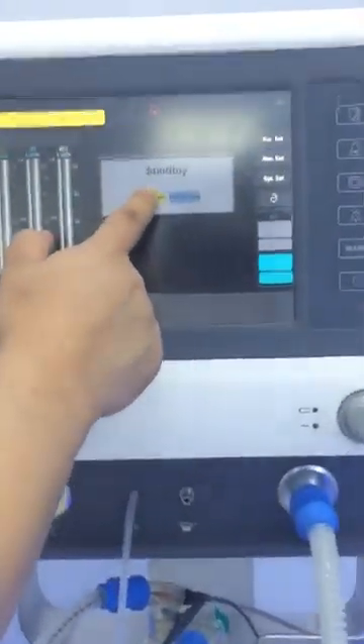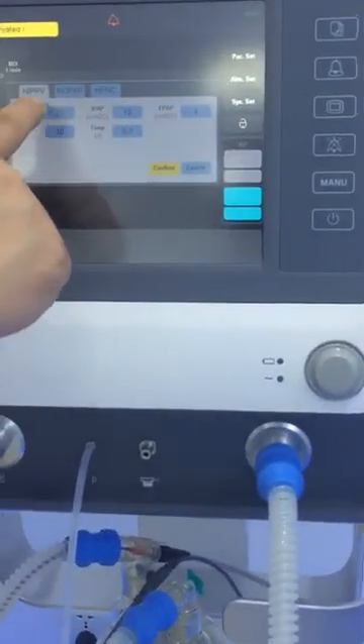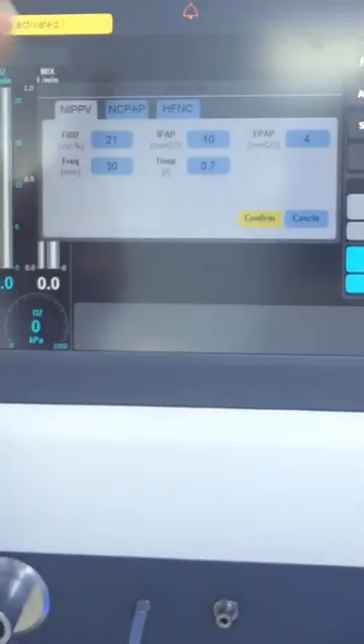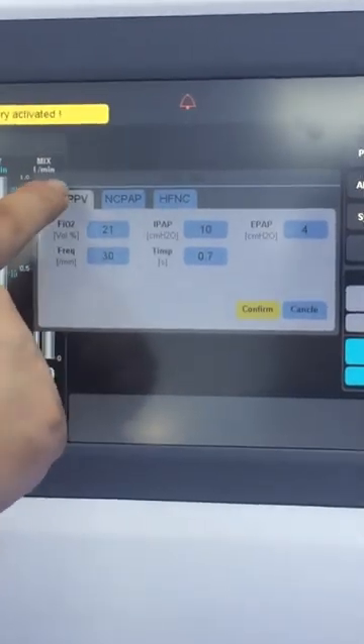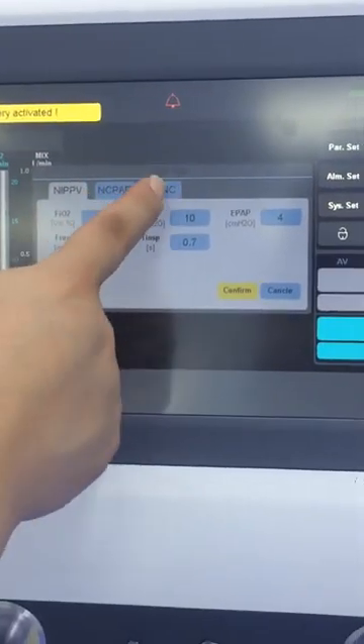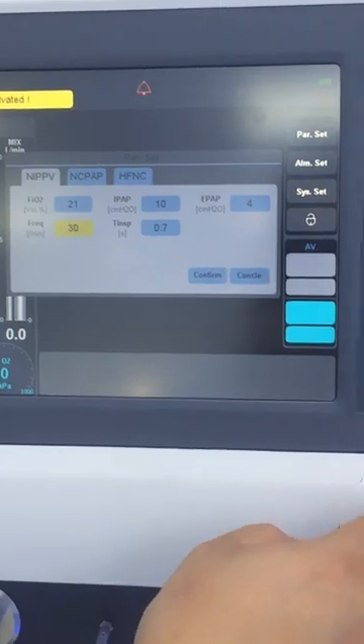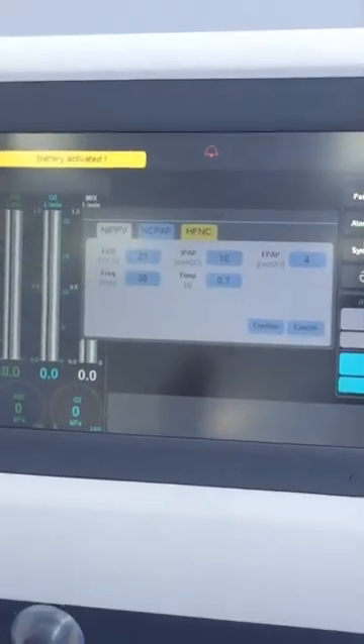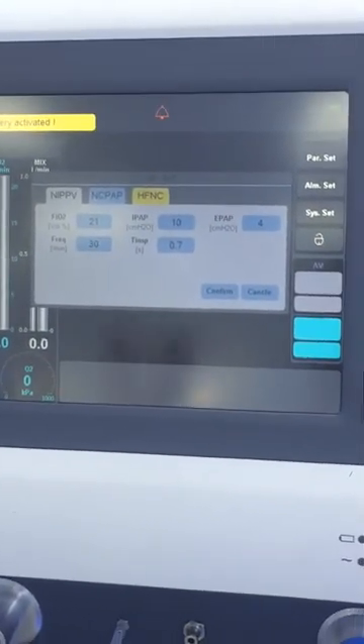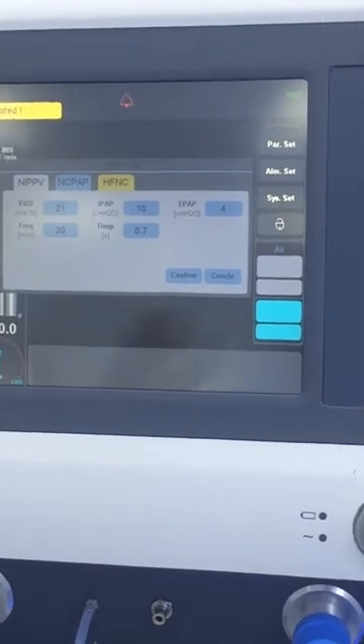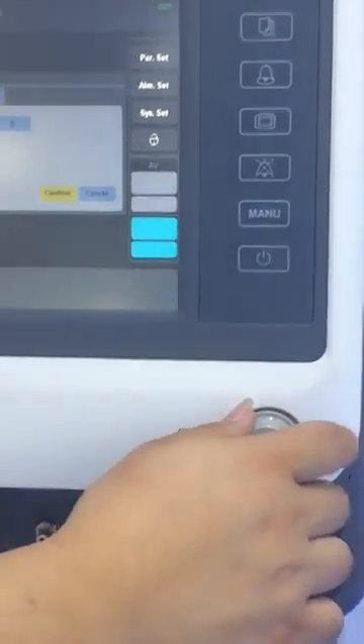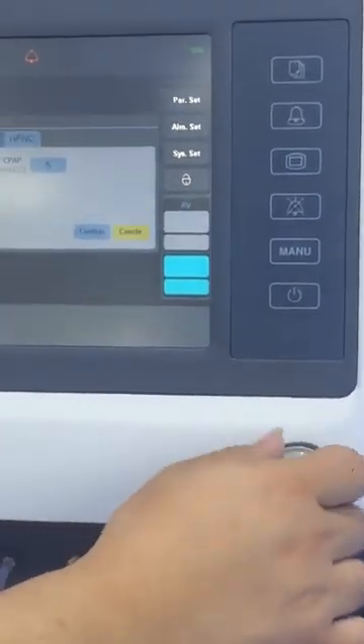For example, now we choose the single tube, and we touch the screen, and then we can first preset the ventilation mode and the parameters. As you can see, under the BiPAP function, we have NIPPV, NCPAP, and HFNC. So there are several kinds of ventilation mode. HFNC means high flow, which is used when a neonatal or infant patient is in some emergency situation, and we use the high flow to make sure the inspired gas gets into the baby's body. Then here is the NCPAP, and here is the NIPPV.